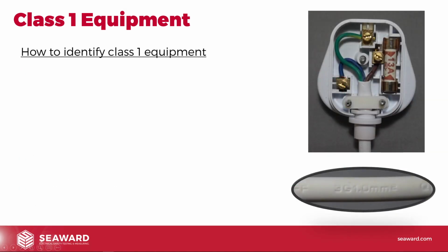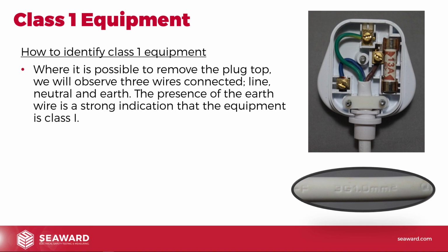Now, how do we identify a piece of Class 1 equipment? Because again, this is one of the hardest bits, actually identifying equipment. So, where it's possible to remove the plug top, obviously we do have moulded plugs now in a lot of cases, but where it is possible to remove the plug top, we will observe 3 wires connected inside the plug. So obviously, you take the plug top off, you have a look inside there. We're going to do that for visual inspection anyway to make sure that the thing's correctly wired. But if you look in there and there's an earth wire connected to the earth pin, that's generally a very good indication that that is going to be Class 1 equipment.